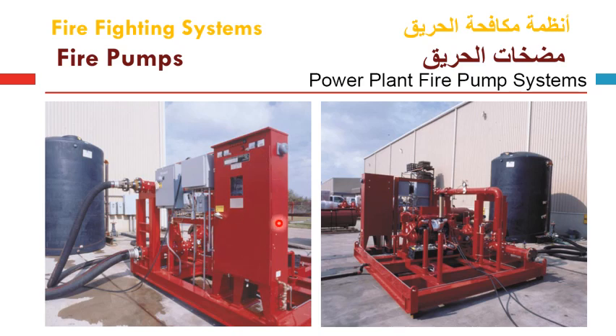And this is the fire pump controller and the electrical MCC, the motor control center, which provides the electrical power supply to the fire controller, and all the monitoring and measuring instrumentation to monitor the performance of the pump in different operation ranges.